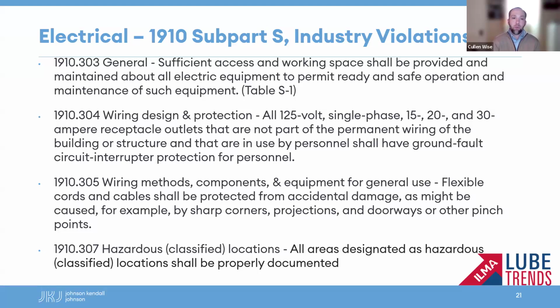1910.305, within this section, we had wiring methods, components, and equipment for general use. This is a pretty common one, what I call low-hanging fruit for OSHA. Flexible cords and cables shall be protected from accidental damage as might be caused, for example, by sharp corners, projections, and doorways or other pinch points. So any damage to flexible cords and cables is something that could be cited. Any use of a flexible cord or cable in a manner that could potentially lead to damage is something that could be cited under the standard. So as it says here, not through doorways, not through wall openings, right, and other methods that could subject any of the equipment to damage.